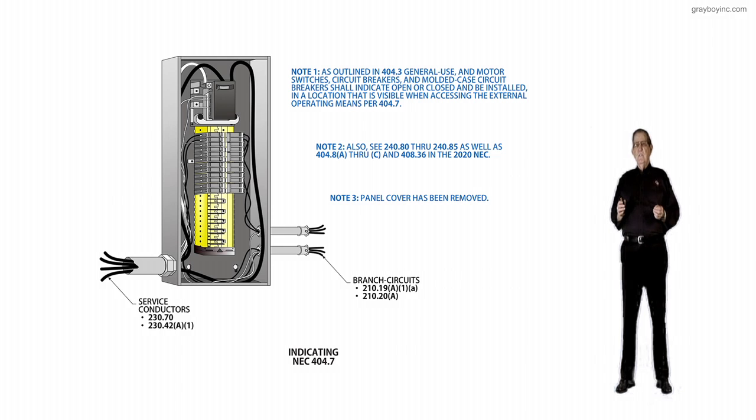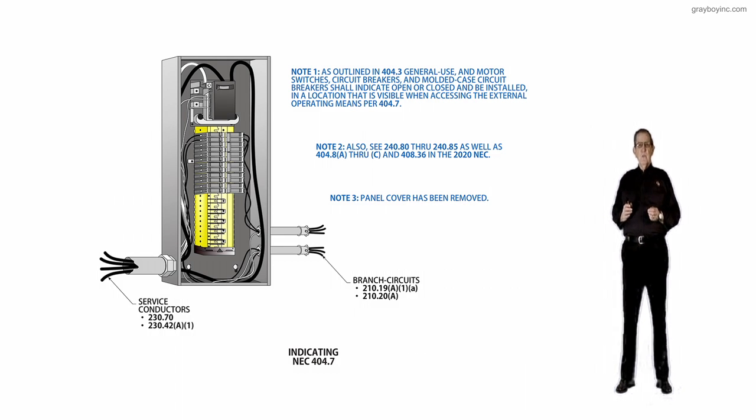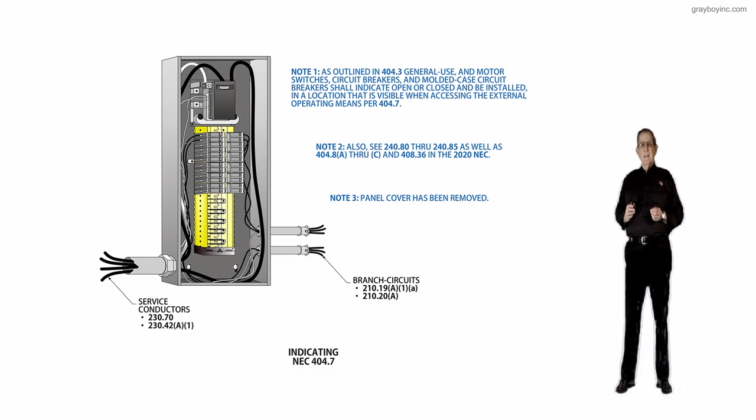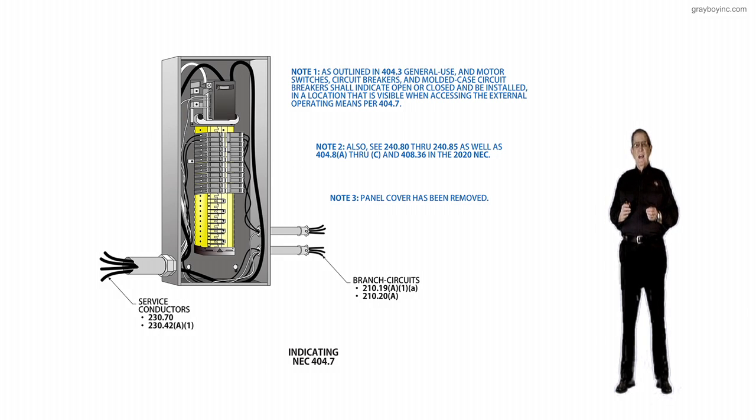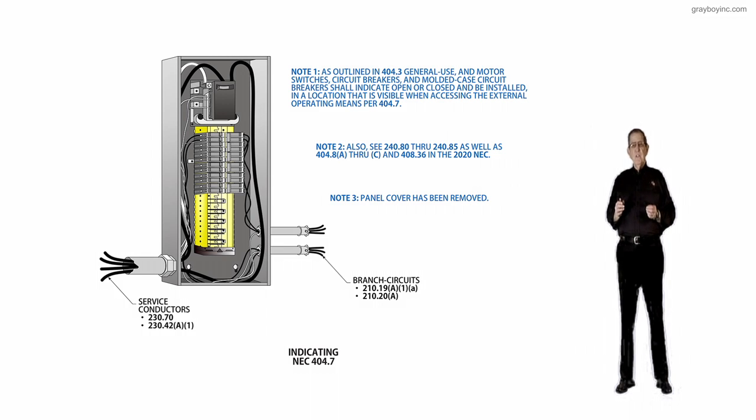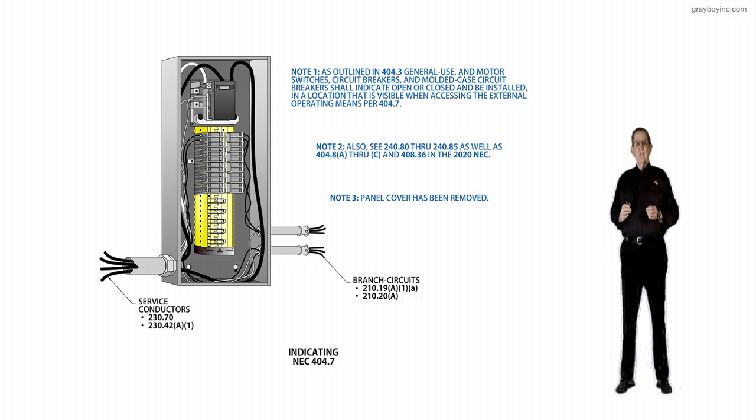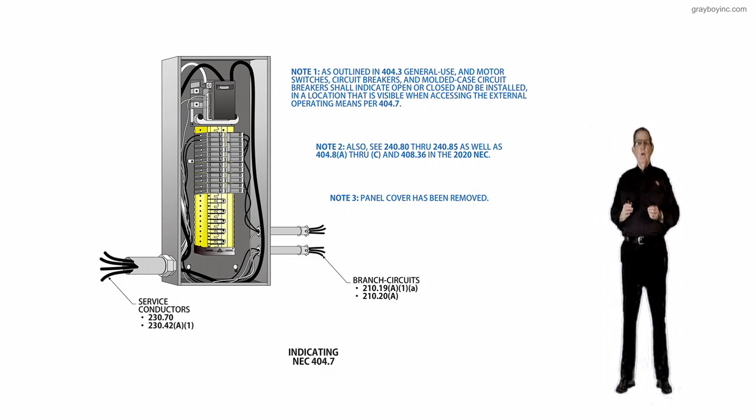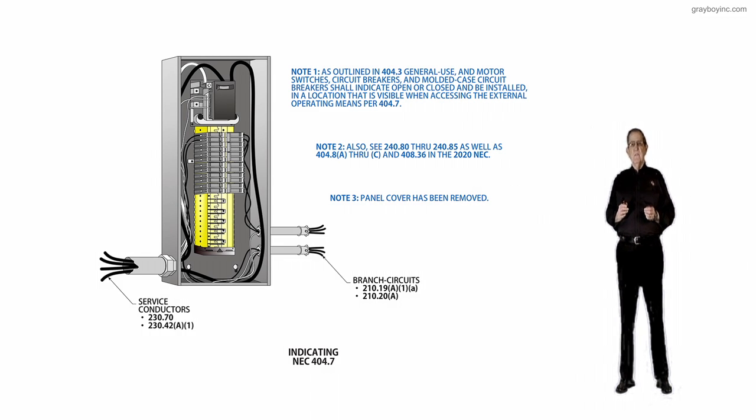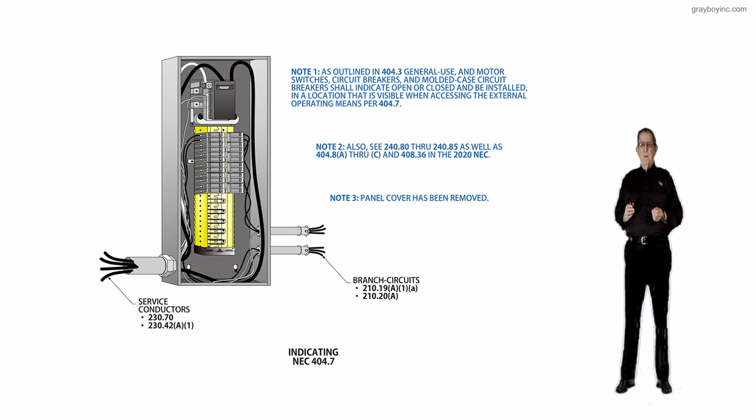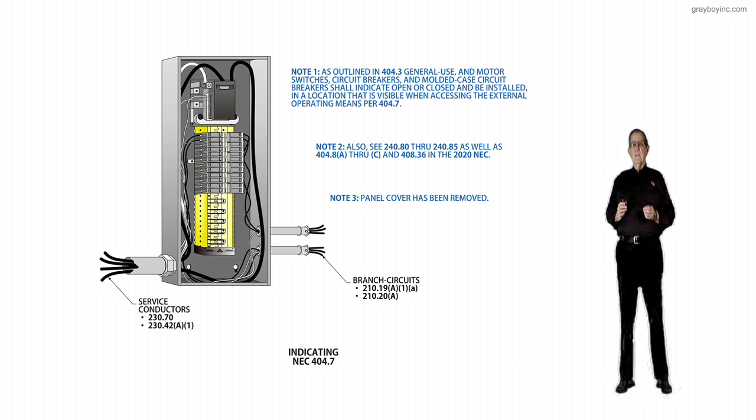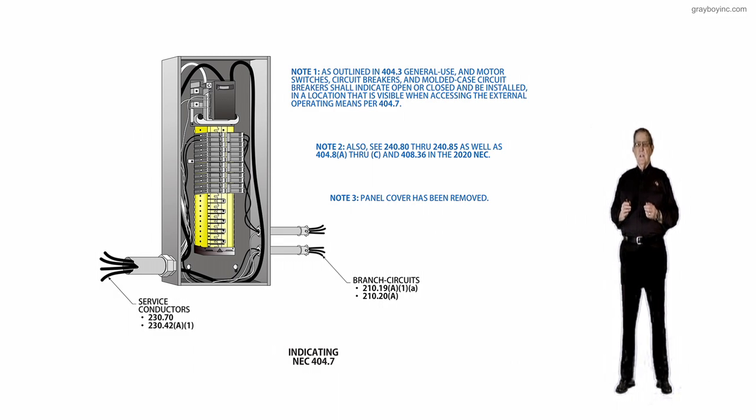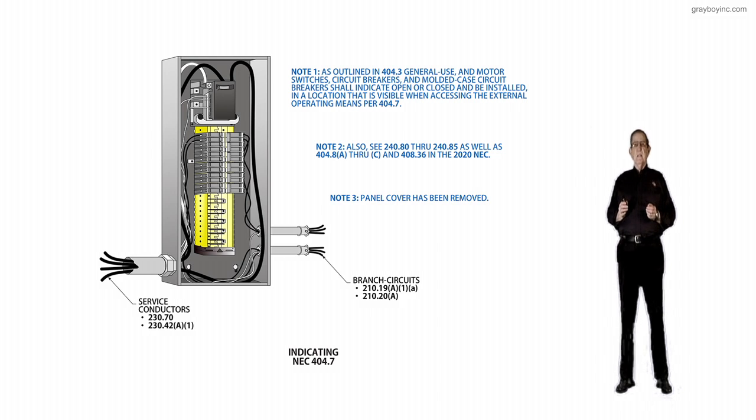Notice that this revision will not affect the switch operating handles behind NEMA 4X and similar enclosures with bolted covers. In such cases, the indication only applies after the cover is open unless the enclosure is equipped with an external operating type handle.